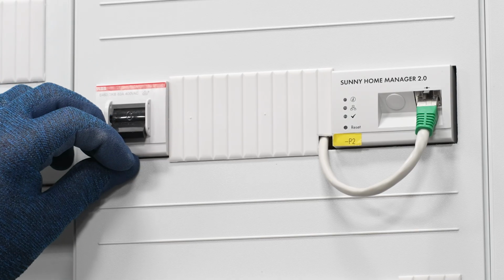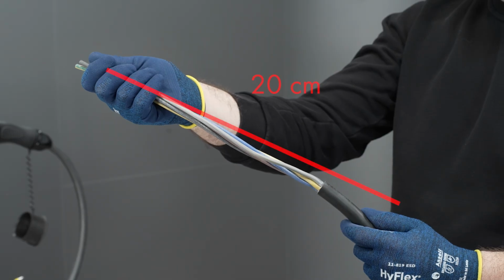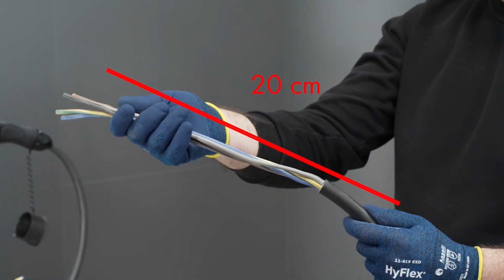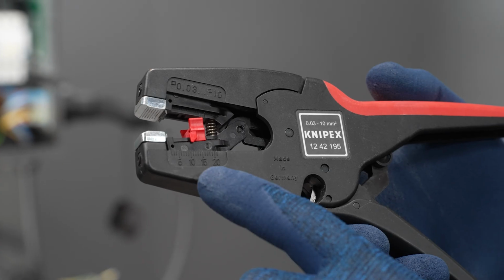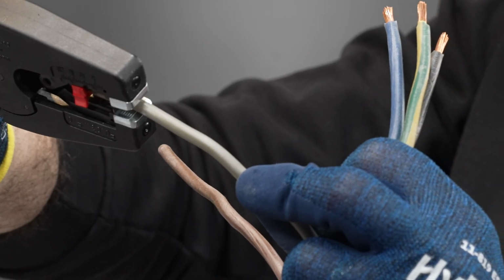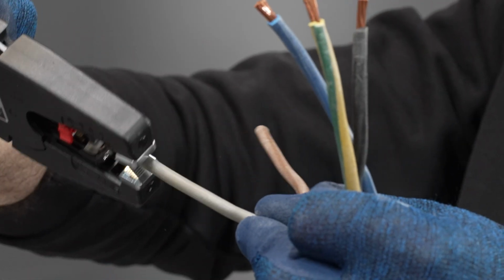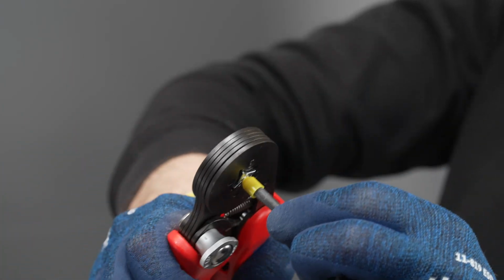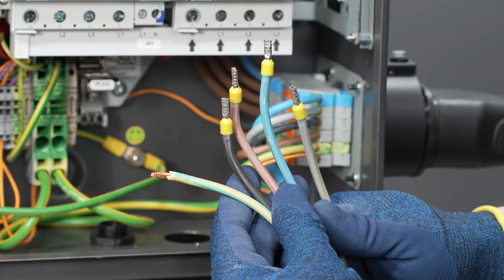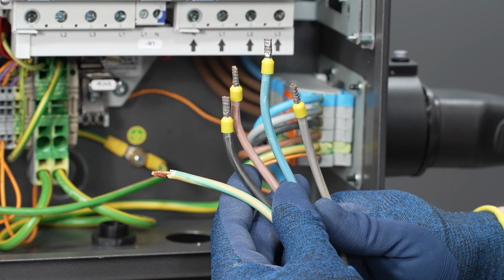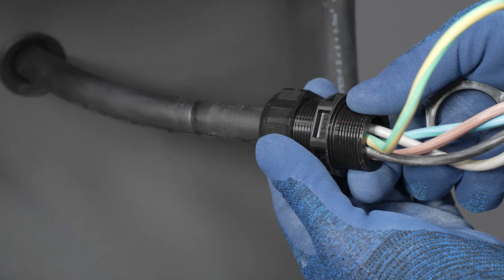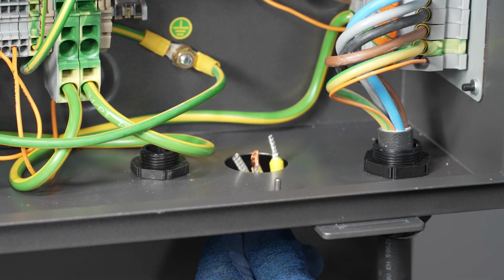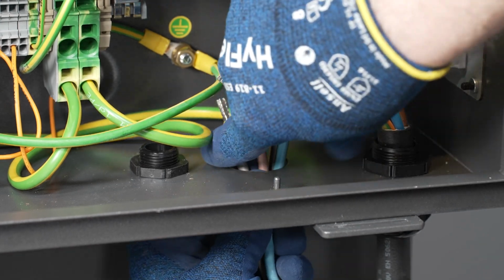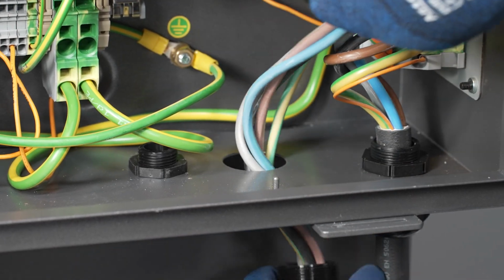Switch off the circuit breaker. Strip 20 cm of the AC cable sheath. Strip 10 mm to 12 mm of insulation from the wires. Feed the AC cable through the cable gland into the product. To do this, loosen the union nut, M32.